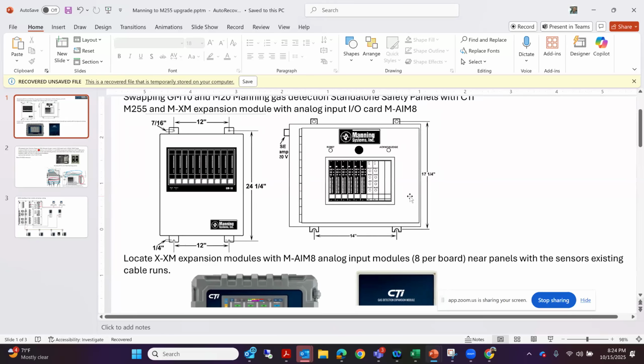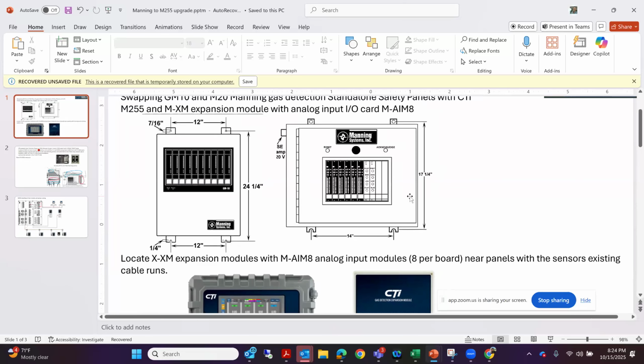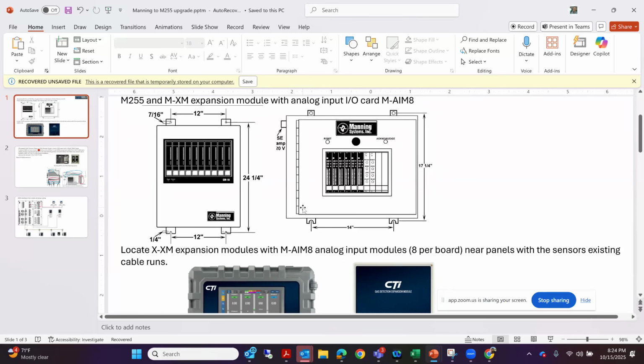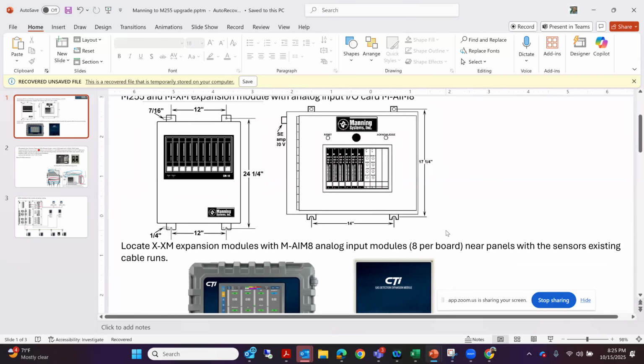So having a standalone system does make it kind of handy, because you're supposed to be calibrating these sensors every 10 or every 6 months. If you had this old system and were full scale testing the output functions, unless they had a bypass key, you were typically shutting down every 6 months. A lot of folks are okay with testing their shunt trip annually, like the codes say. A lot of folks want to test it every 6 months, and that's completely fine. That's being more safe.